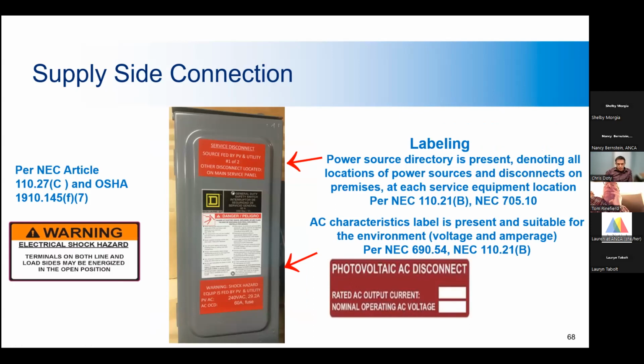So here's some of the labeling requirements for this type of connection. You have a traditional electrical shock hazard label that is probably on every single electrical panel, and you have the PV AC disconnect also. The PV part of the code has some of the heaviest requirements for labeling that there is, and it's important to maintain the safety of the system, so definitely familiarize yourself with that part of the code.